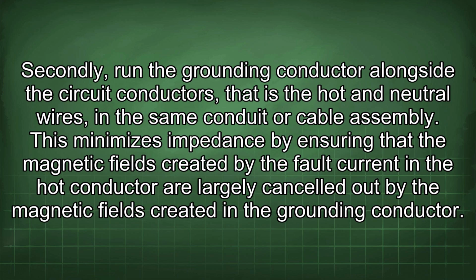Secondly, run the grounding conductor alongside the circuit conductors, that is the hot and neutral wires, in the same conduit or cable assembly. This minimizes impedance by ensuring that the magnetic fields created by the fault current in the hot conductor are largely cancelled out by the magnetic fields created in the grounding conductor.